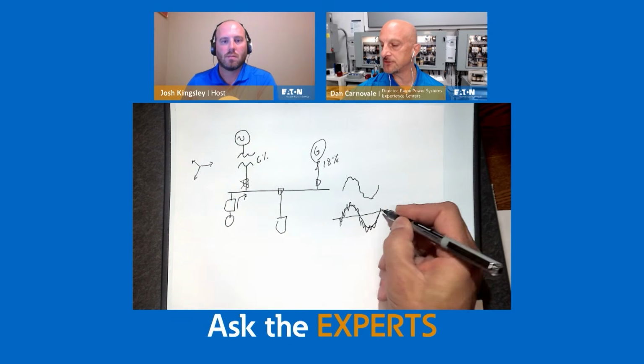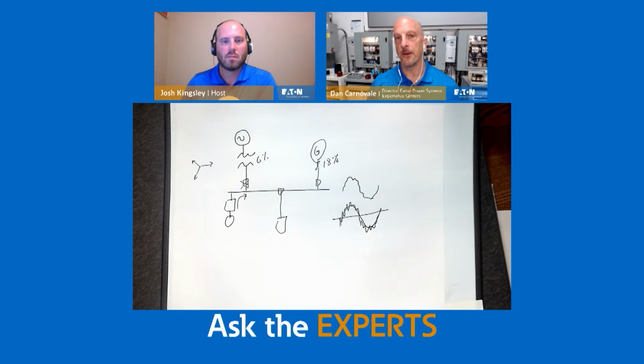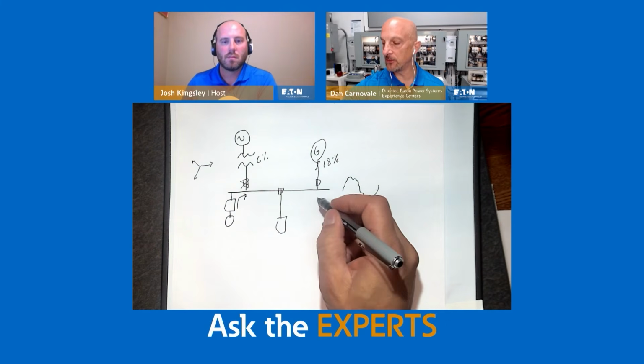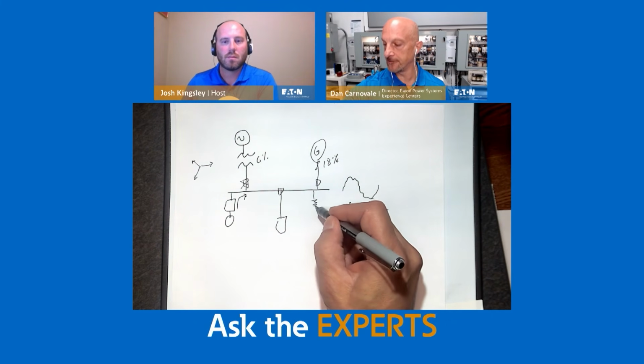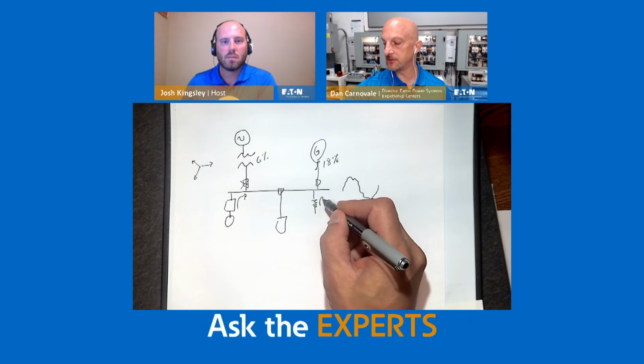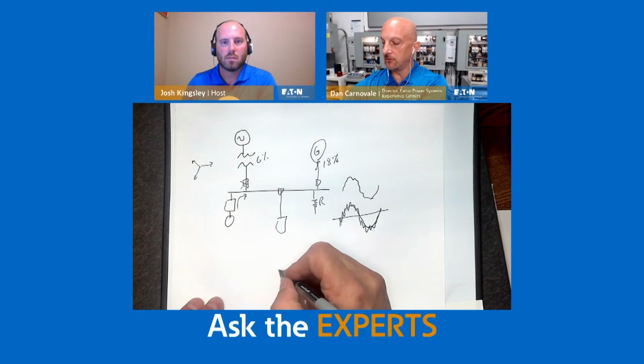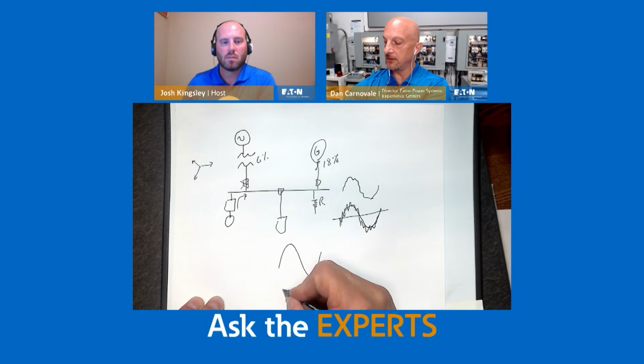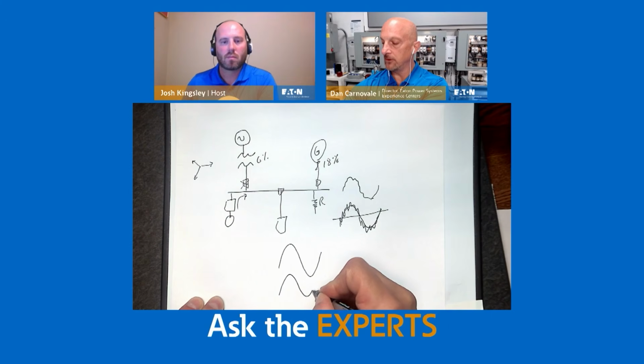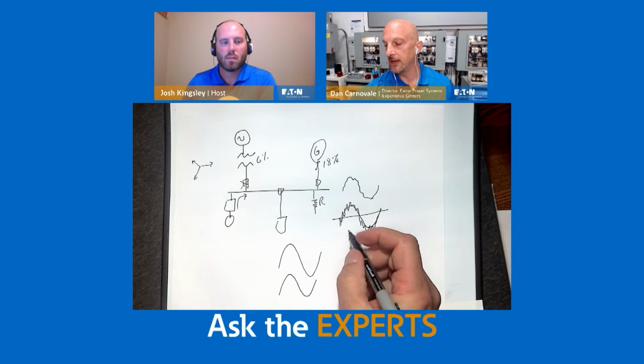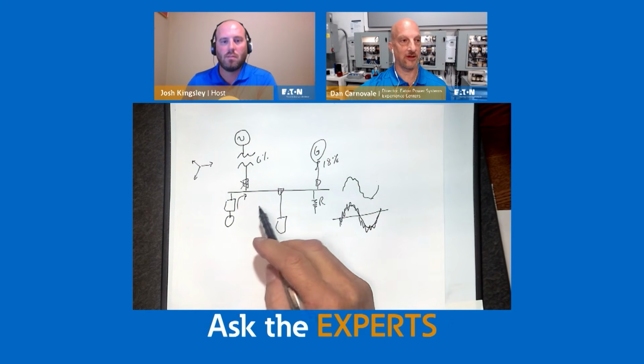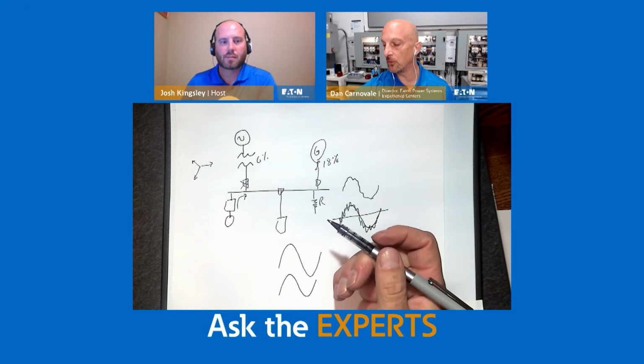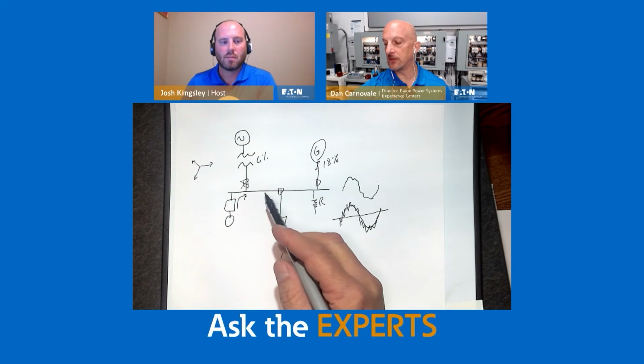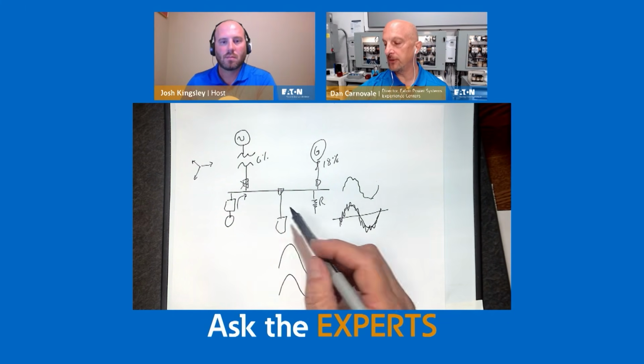And what's really interesting, Josh, you kind of made me think of something. What do people usually test a generator with? They'll bring in a resistive load bank and they'll test it with a resistor. Well, of course, if you have a linear voltage and you have a linear current, you have no distortion. It's going to look fine. And then they have a real scenario where the power goes out and they're running on the generator and they have a problem. So this is something that I have run into a lot and people need to deal with.